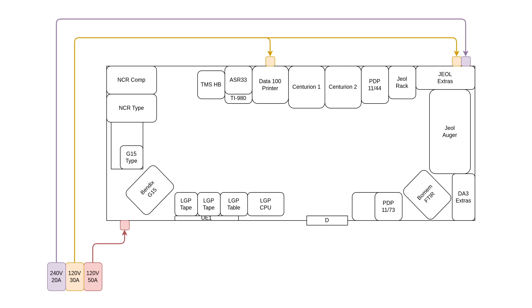Looking through the manual about what it takes to install this thing, it says the power supply is single phase 100 volt 30 amp and 200 volt 20 amp at 50 or 60 hertz. So the 30 amps we're running to the Centurion, we're going to continue to run clean over to here, so that way I have 120 volt 30 amps ready for this. We're also going to run 240 volts along pretty much the same path as that dedicated 30 amp circuit, and get that all the way into this corner as well. We're not going to wire up any sockets right now, just get the wires there for the future. But the big problem is that it's 100 volt and 200 volt.